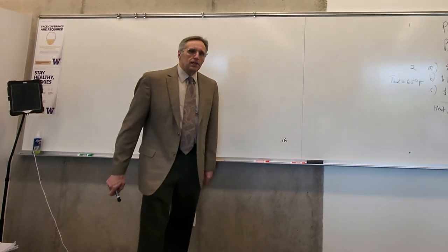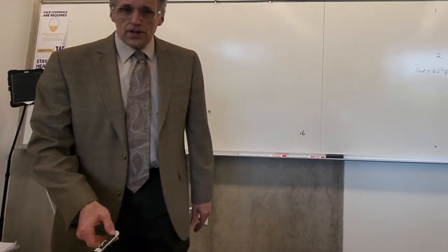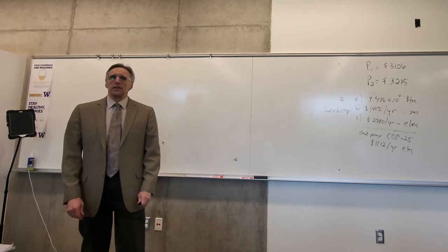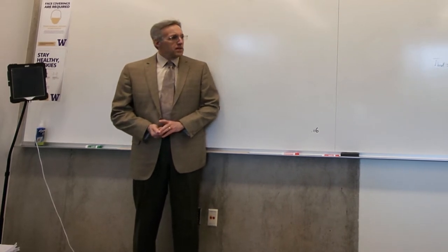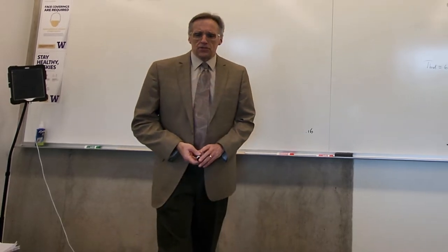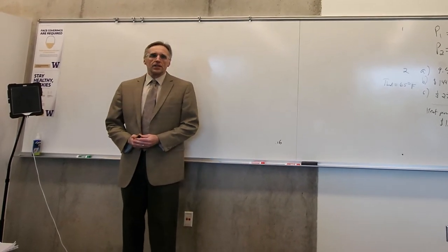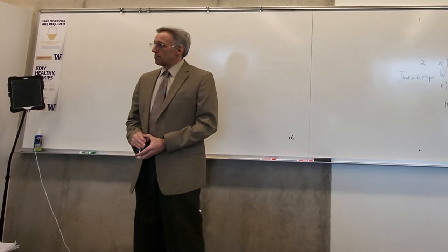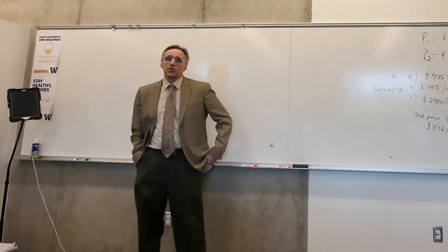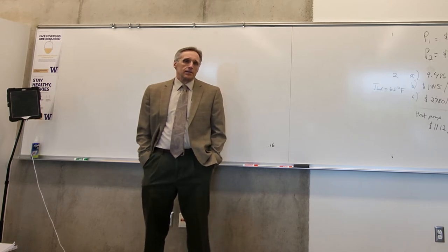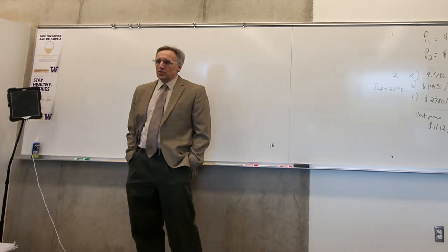Now, one of the groups, you guys are looking at the heat pump at 21 acres, and they're using it for water heating, and they're trying to get water to 140? Yeah. I thought about that over the weekend, and I was looking up through some of my technical material, and that strikes me now, as we're talking about Friday, as a very, very difficult application. R410, which is the refrigerant used in most heat pumps today, really only works well up to about 140 degrees. That's the refrigerant temperature, at 400 to 450 psi on the pressure at the condenser, and that's a really high pressure.